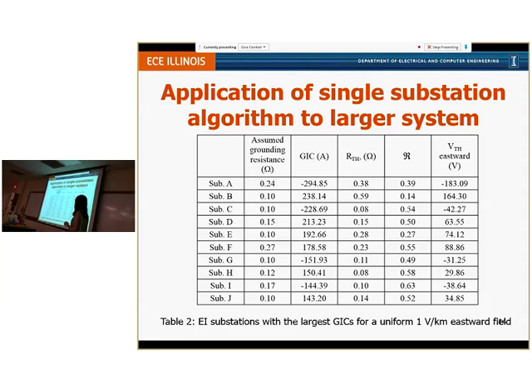This is the table that shows the normalized variation of the top 10 substations that have the highest GIC in the system. In this table, we can see that 6 out of 10 of them have a normalized variation of more than 0.5, which means that the grounding resistance dominates in determining the value of the GIC. And this is not just in these 10 substations. We saw that in the top 100 substations, the average normalized variation is 0.47, and in the top 500, the average value is 0.51. From that, we can see that the sensitivity of the GIC to the grounding resistance cannot be ignored. It's significant.